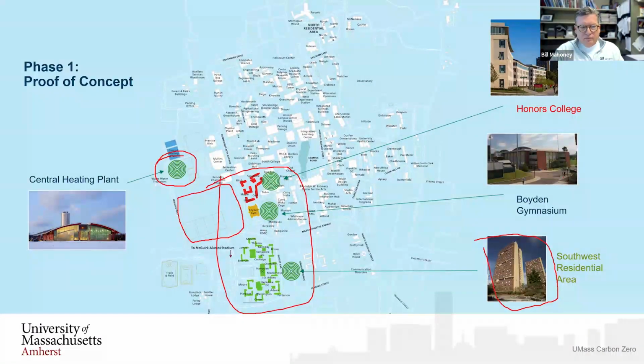So heated only. So when we've talked about this in these other decarb debriefs, in the Northeast it's tough for a ground source heat exchanger system, which is what they wanted us to do here, if that wasn't clear. It's tough in the Northeast because there's a climatic imbalance. The energy for the heating system over the course of the year will require more BTUs than the BTUs that your cooling system, for a given amount of buildings heated and cooled, will put into the ground in the summertime. So that's always going to be an issue in New England.